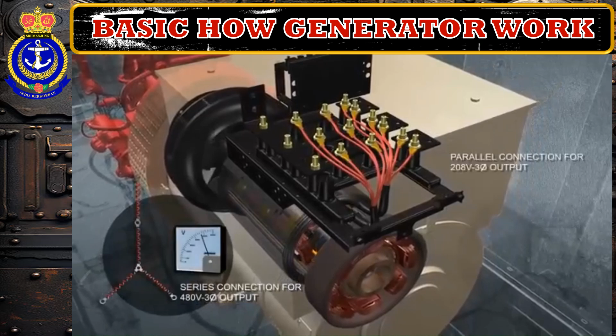Doosan mobile generators also include alternators with 6 coils wound into the stator. This provides 3 voltage sources, or phases. Because each phase combines 2 coils of wire, the sources can be connected in series for high voltage applications or in parallel for low voltage needs.